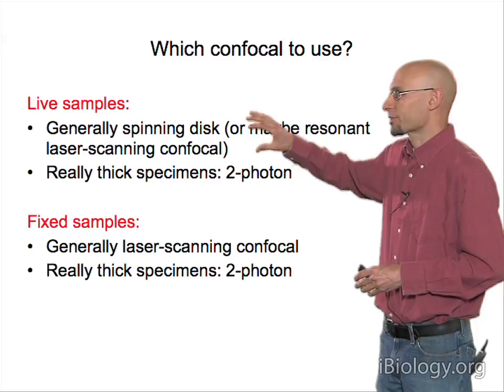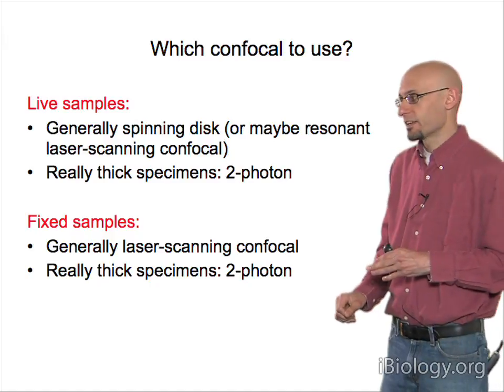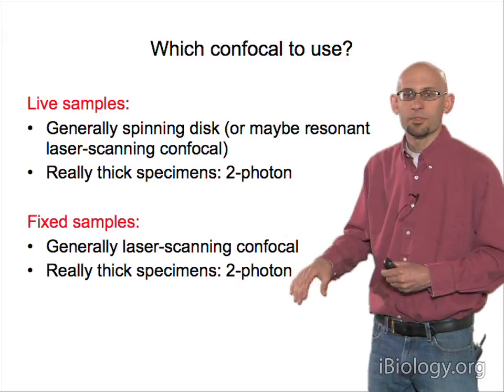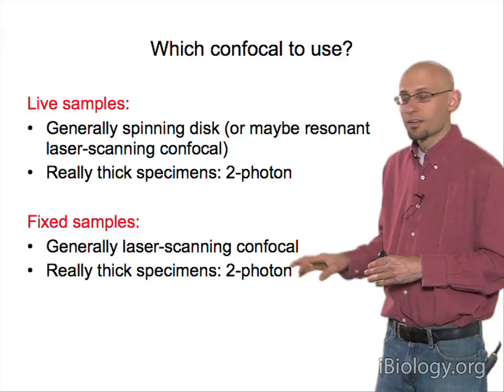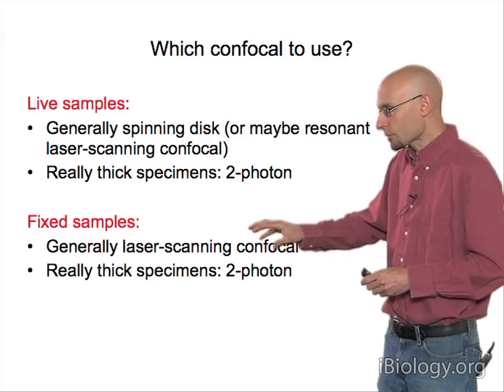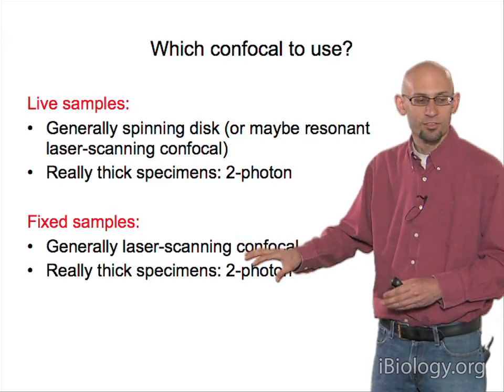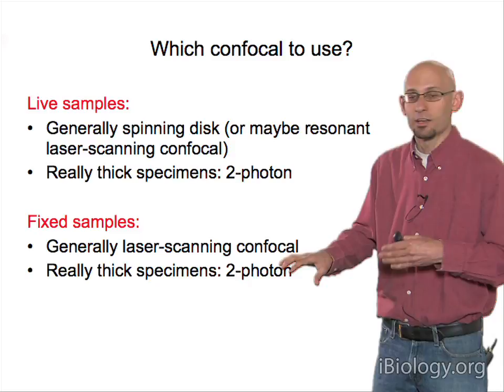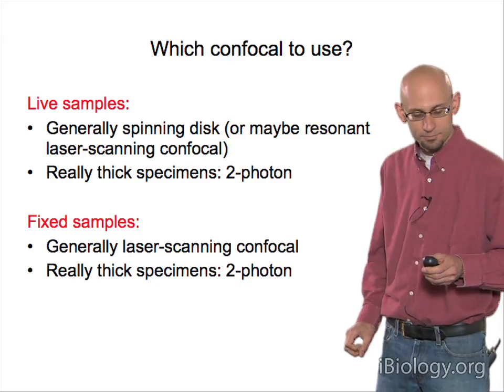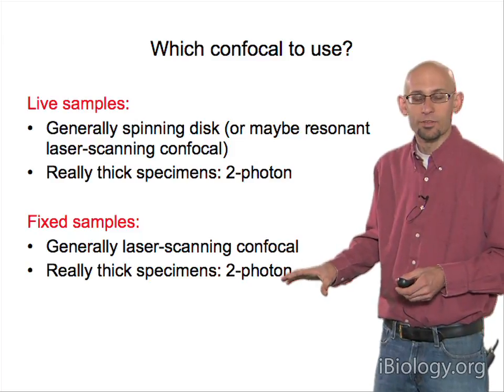Which confocal do you want to use? For live samples, generally use spinning disk, or consider resonant laser scanning confocal. For really thick samples like tissue explants or imaging into a live mouse, two-photon really shines. For fixed samples, generally start with a laser scanning confocal — sensitivity is less of a concern since photobleaching and phototoxicity are non-issues. For very thick fixed specimens, you would also consider two-photon. If you have access to both types, try both to see which works best.